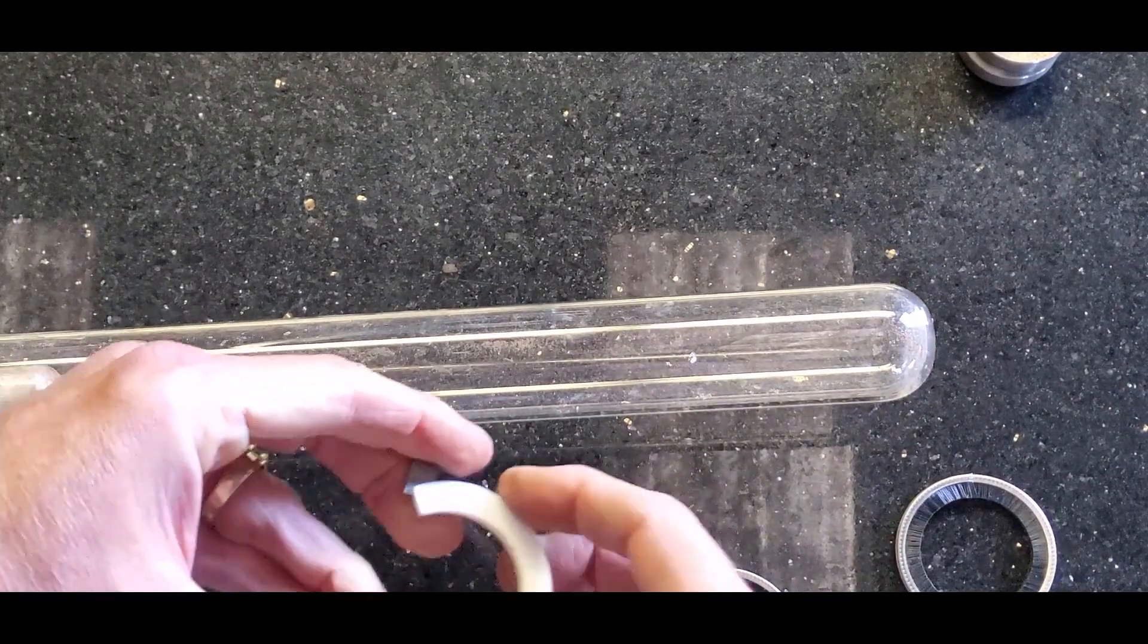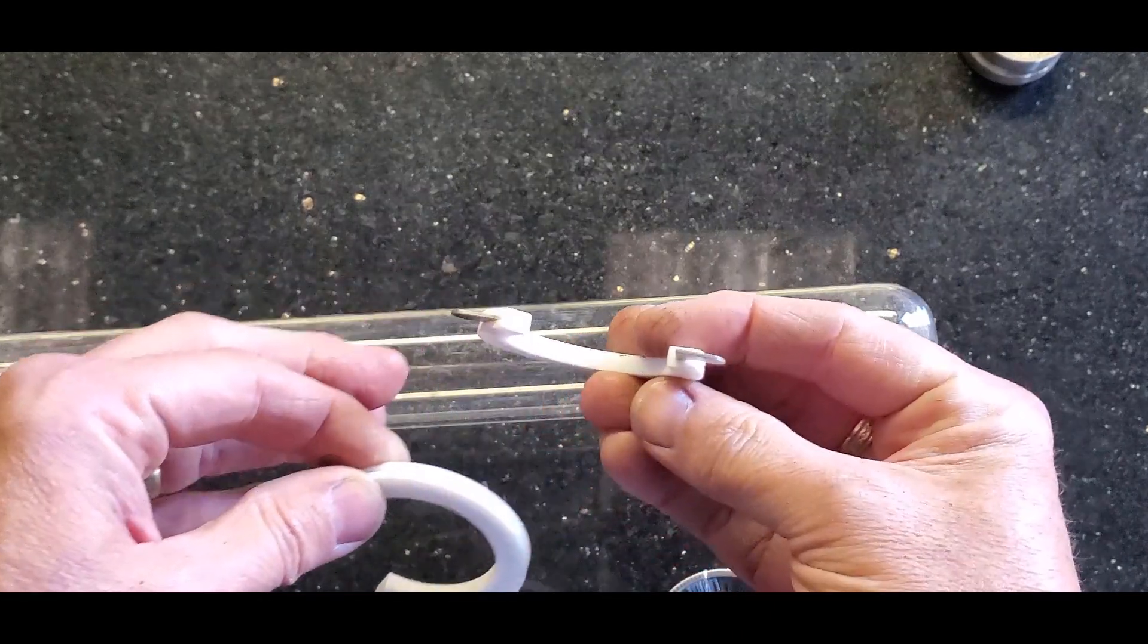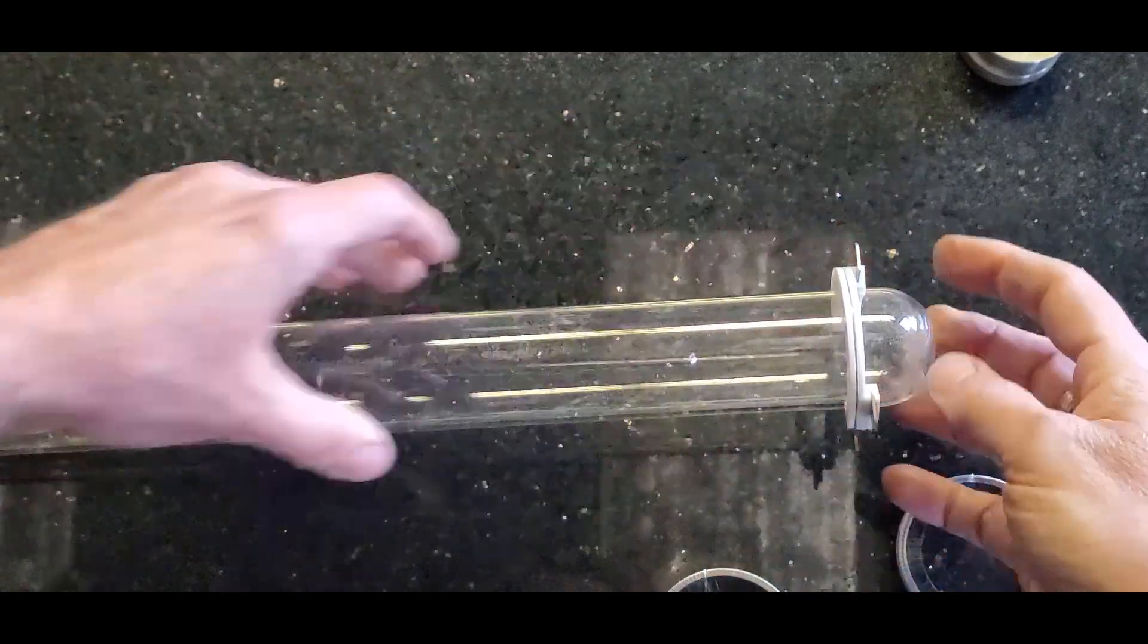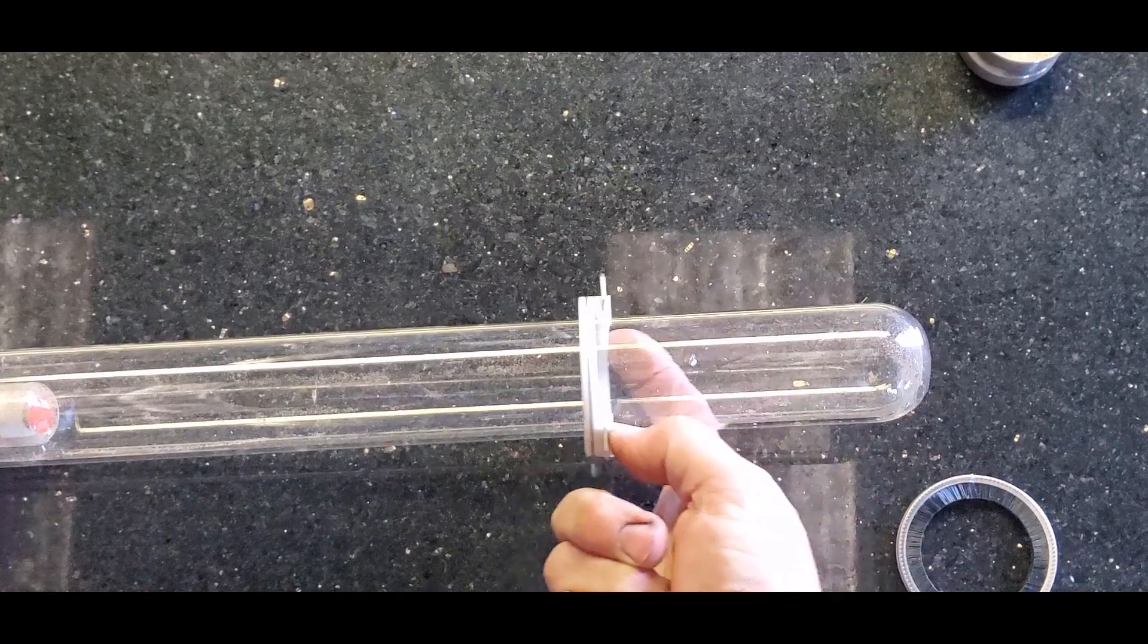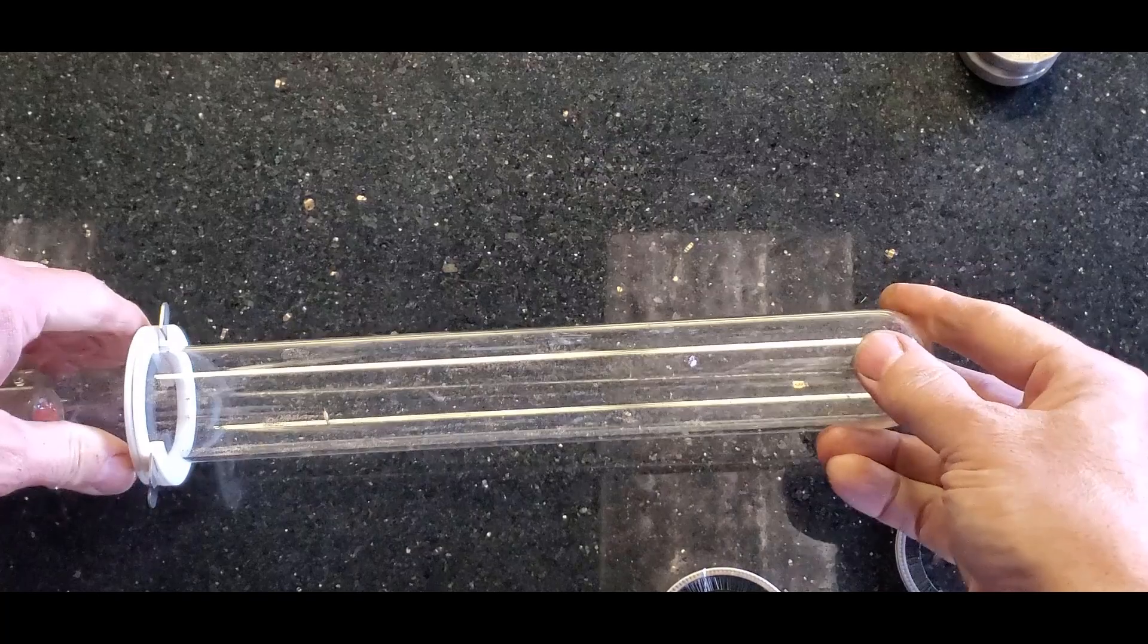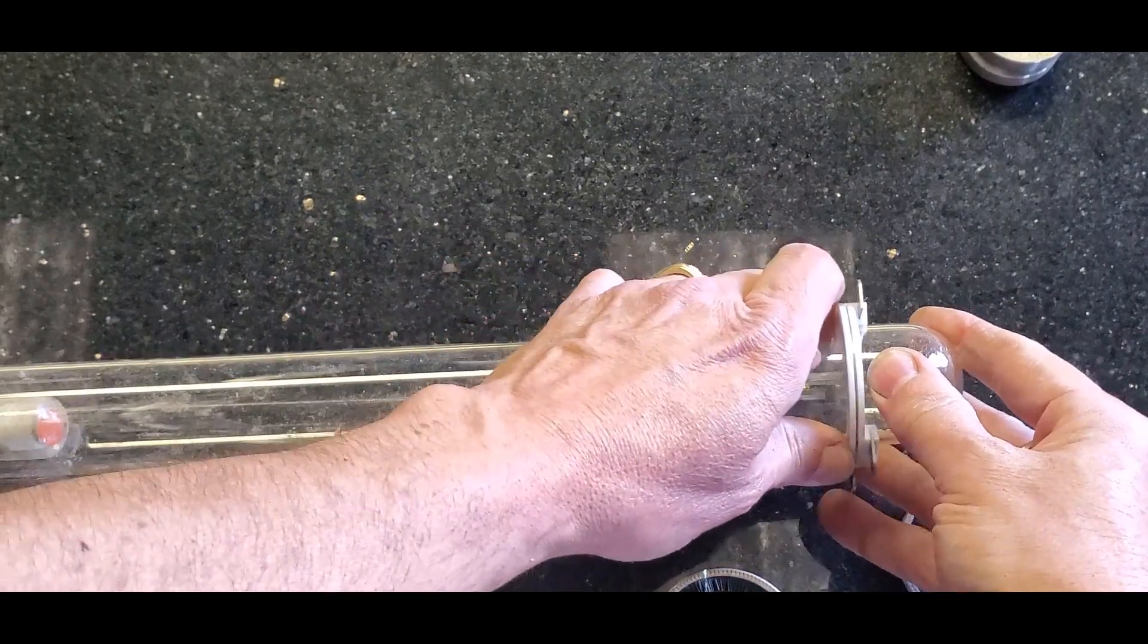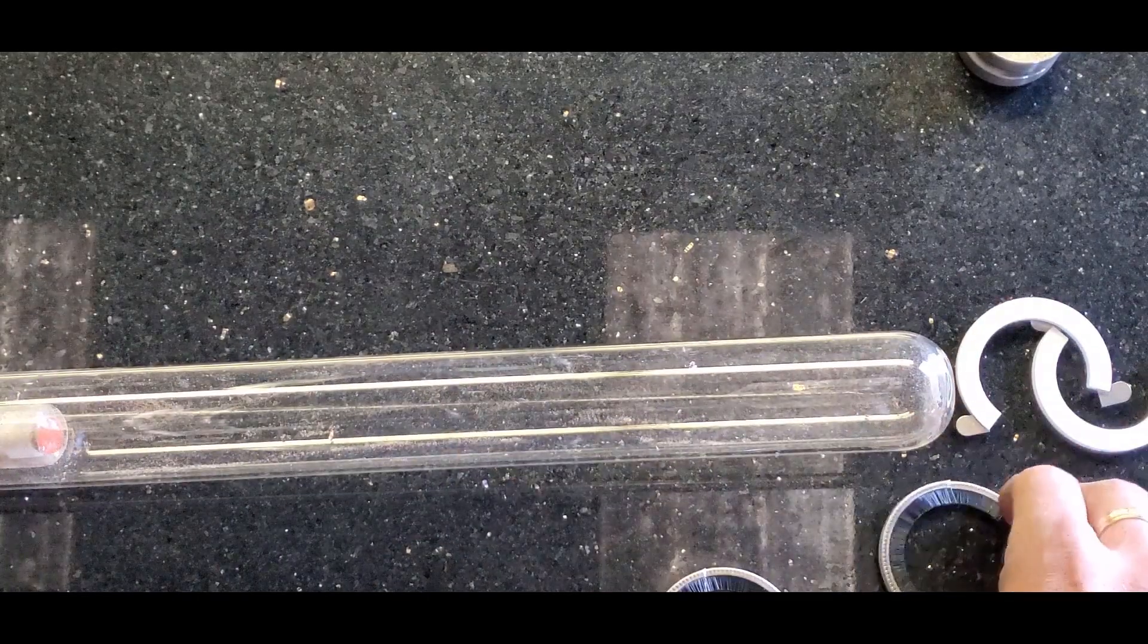I've tried other things - this is a Teflon wiper with a stainless steel tensioning ring, and you put two of these together and the Teflon wipers have a sharp edge so they scrape the surface of the tube clean. Because what happens is all this wastewater is flowing on here - the bodies of these bacteria and viruses, they're either sticky or they're slimy and they build up on the surface of the quartz tubes and start to block the light so it has to be wiped.